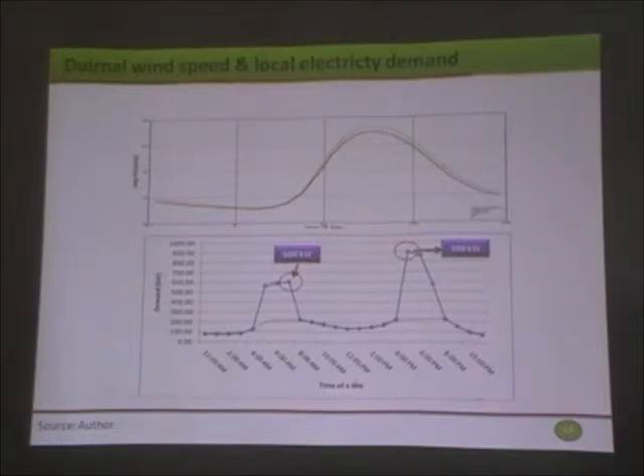Looking at the correlation between local wind conditions and local demand, the correlation is not very strong. It is partially correlated in the evening, but in the morning there is no wind, so there is limited possibility to use wind energy in the morning. This justifies the need for another energy system for better reliability of power supply in that area. The peak demand in the morning is around 600 kilowatt and in the evening is 900 kilowatt.